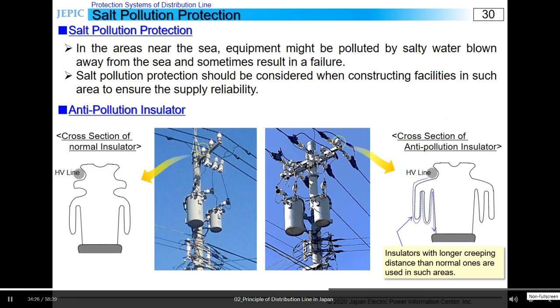Next subject is salt pollution protection. In the area near the sea, distribution equipment might be polluted by the salty water blown away from the sea, and it sometimes causes a failure due to poor insulation or deteriorated equipment.